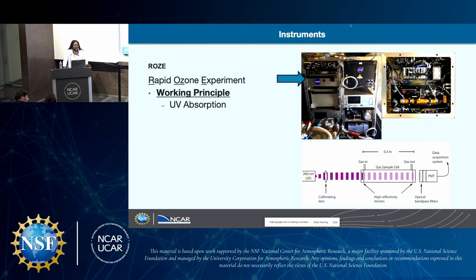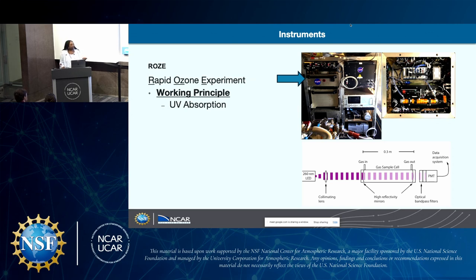ROZE is actually a little bit different. Its working principle is that it uses UV absorption. We use a LED at 260 nanometers and shoot it through our gas sample, because ozone is known to absorb this wavelength of light. We use two mirrors to keep the light from escaping, and then the light is measured with a photomultiplier. ROZE is different from the other two instruments in that instead of the PMT measuring how many photons are released, we're measuring how much is absorbed by the ozone.